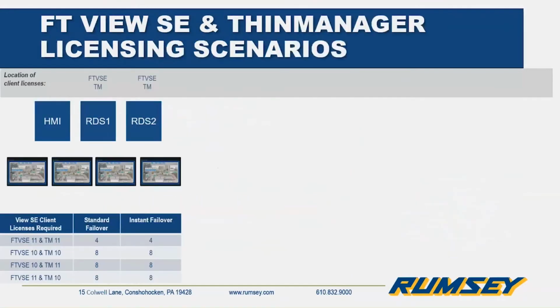So let's take a look at a few different instances here. We'll look at a fairly simple one first. We have our HMI server running FactoryTalk View SE. We have 2 remote desktop servers, RDS1 and 2. Each one has ThinManager on it, so we have a redundant ThinManager pair. And we have those remote desktop sessions. They're co-located there, and they're running our FactoryTalk View SE client session. I have 4 Thin client devices out on the plant floor. So what that means is I would need 4 SE client licenses, 1 for each device.